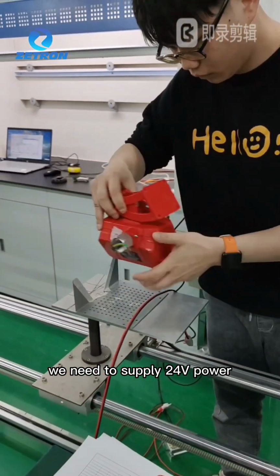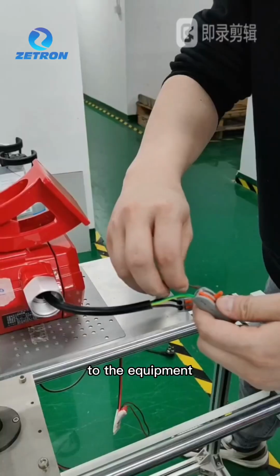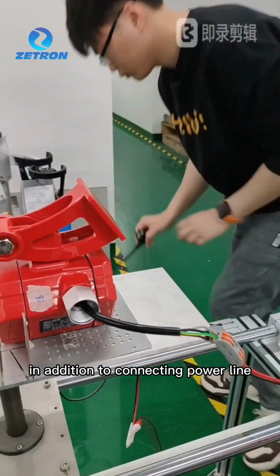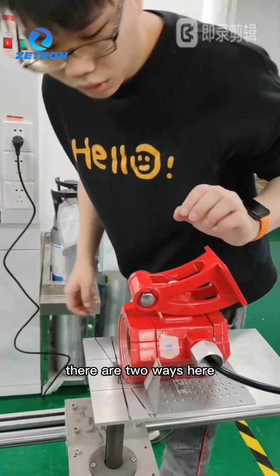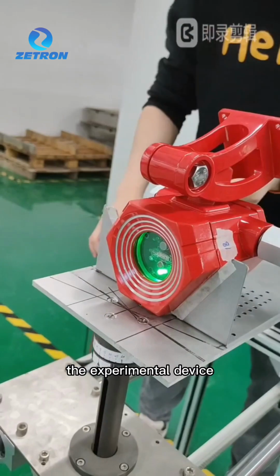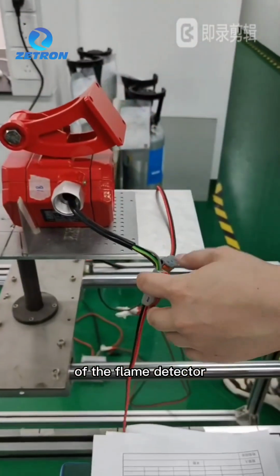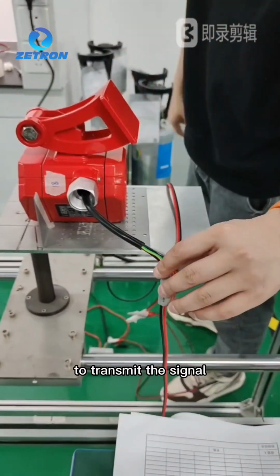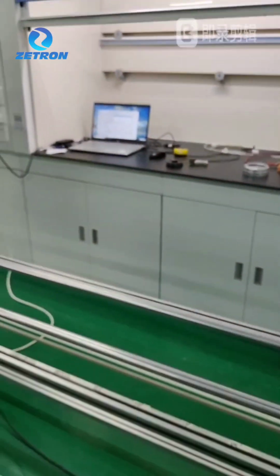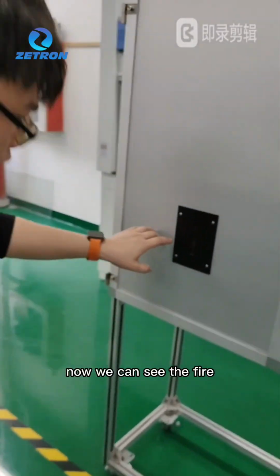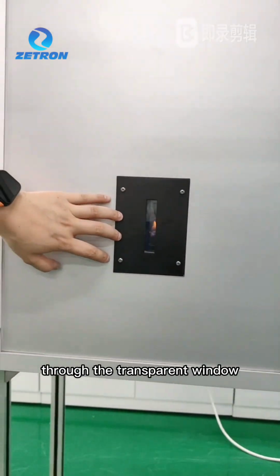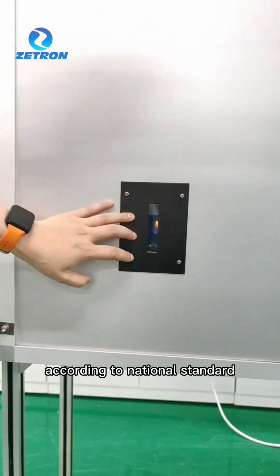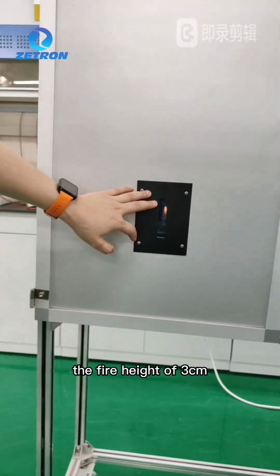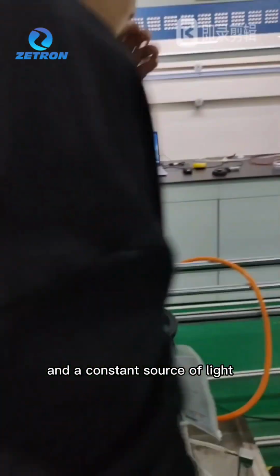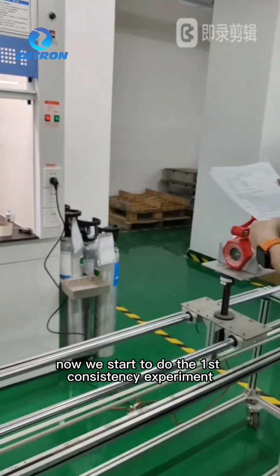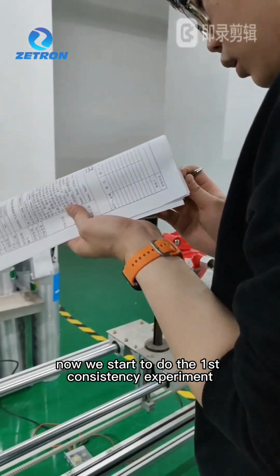First of all, we need to supply 24-volt power to the equipment. In addition to connecting the power line, there are 2 wires here to connect with the experimental device of the flame detector, to transmit the signal and control the distance. Now we can see the flame through the transparent window. According to the national standard, the flame height is 3 cm with a consistent source of light. Now we start the first consistency experiment.